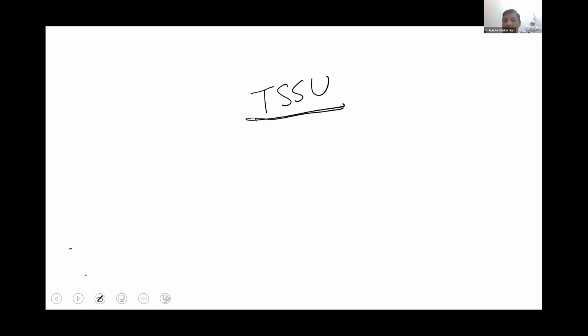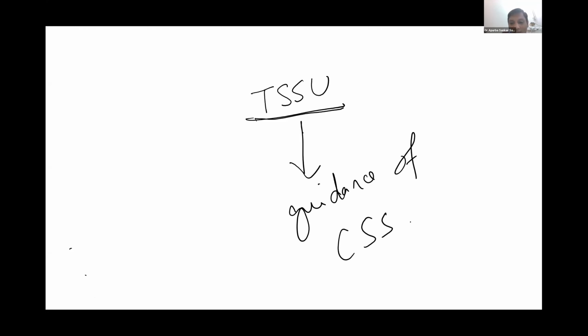Otherwise, in general situations, it's recommended not to have a TSSU. However, our general practice is that surgeons or healthcare workers find it very easy if the TSSU is located next to the operation theater, but it's found that most often TSSUs are mismanaged. So TSSU should be kept only when it's essential, that is, when you have a big, large hospital. Even then, the TSSU has to be under the guidance and direct supervision of CSSD. It cannot function separately; you can't have two different bodies.